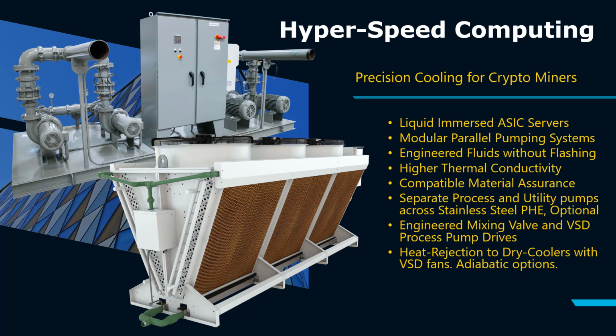There's a high velocity of fluid that is flowed across the servers, and it is directed to directly and most effectively cool the processors. There are separate process and utility pumps across plate and frame heat exchangers as an option. That can also involve an engineered mixing valve with VSD process pump drives. And the heat rejection can be to dry coolers with or without adiabatics. They typically do have VSD fans.